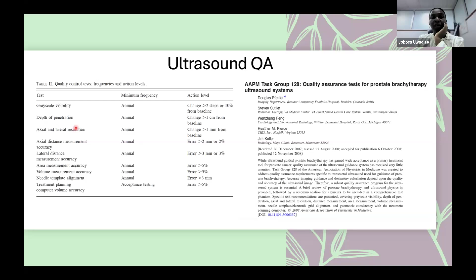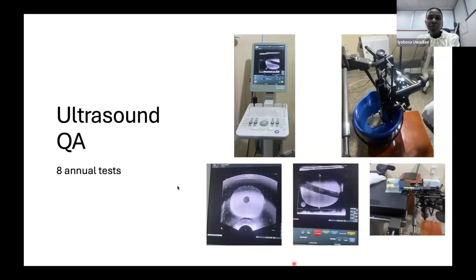moving on. So we do all the other tests: the area measurement accuracy test, volume measurement accuracy test, contouring test, and all that. We have a prostate phantom, this small one that you can see on the screen, which we use for our area and volume measurement accuracy test, as you can see on these images. For the needle placement accuracy test, we do not have the CIRS phantom, but we can use a bucket of water, as you can see on the screen, which is what we do. So we do all these tests once in a year, or for teaching purposes, we can do that as needed.